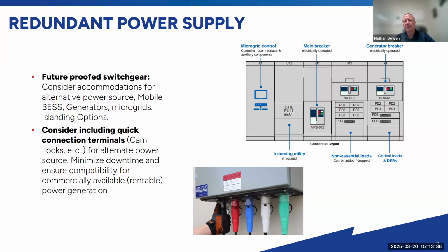One thing to think about, if battery energy storage or microgrids are on your roadmap, is the bus sizing in the gear itself to make sure you can handle the ampacity, and looking at the mains to make sure you have bi-directional overcurrent protection, things like that.